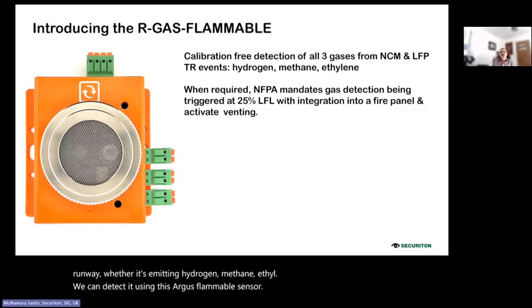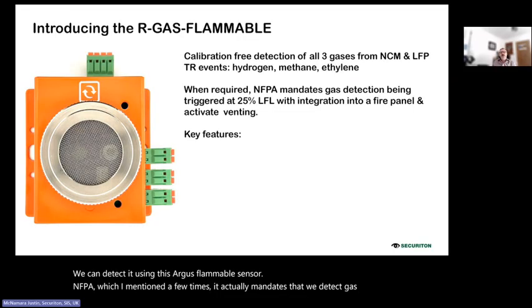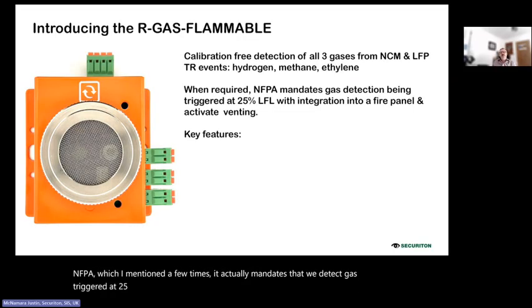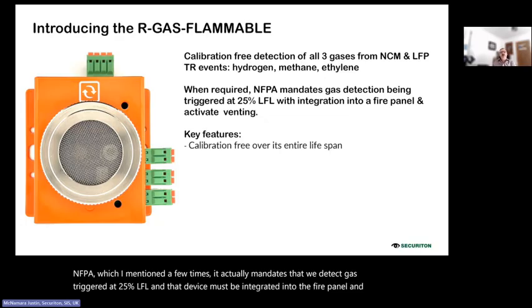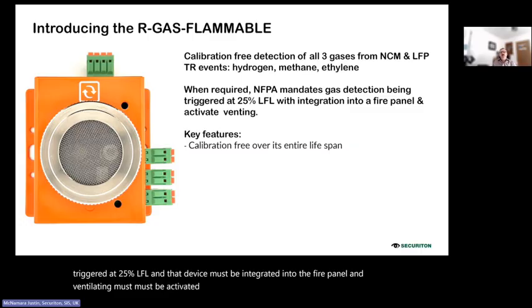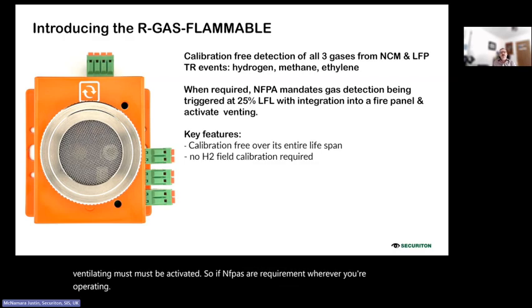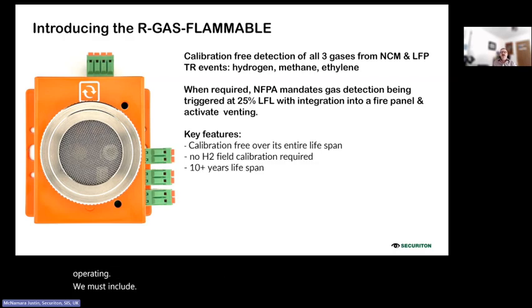NFPA, which I mentioned a few times, actually mandates that we detect gas triggered at 25% LFL, and that device must be integrated into the fire panel, and ventilation must be activated. So if NFPA is a requirement, wherever you're operating, we must include flammable gas detection.